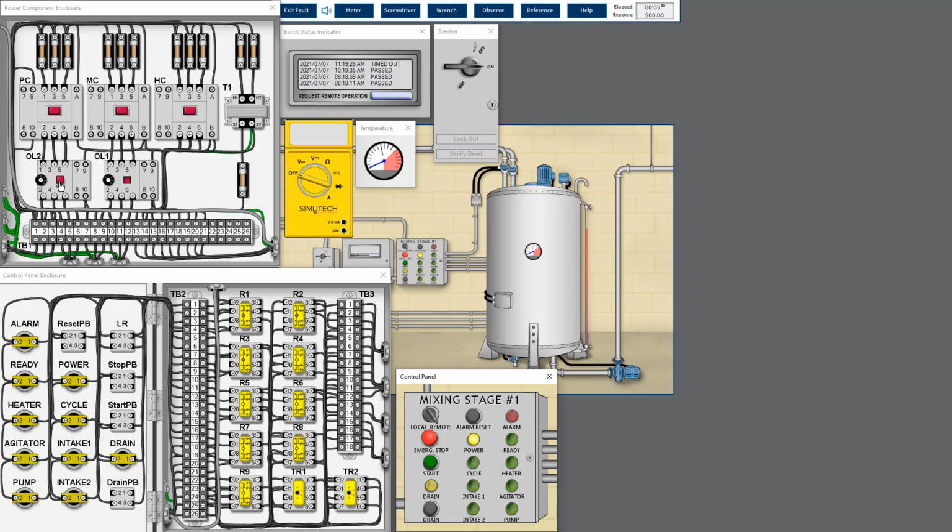There's a button popping out, meaning an overload happened, whether it is a mechanical overload, electrical overload, or process overload. As for electrical overload, it refers to single phasing or one phase open along the line. It can be the fuse, wire, contactor, overload relay, or the motor winding, or even a loose termination. As for mechanical overload, it can be due to the pump, impeller, or motor bearing seizing, or the conveyor belt being too tight or too loose, etc. As for process overload, it can be due to the upstream or downstream valve being shut, or a product stuck inside the pump outlet, etc. Most of the time, it's due to electrical overload or mechanical overload, okay?